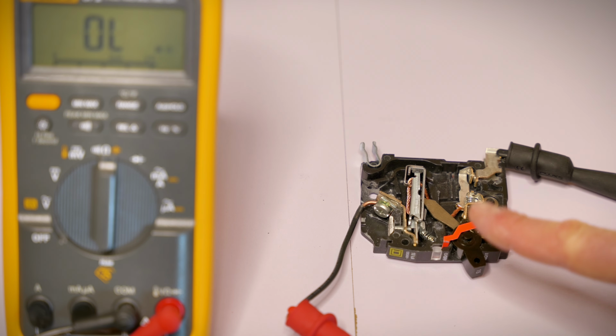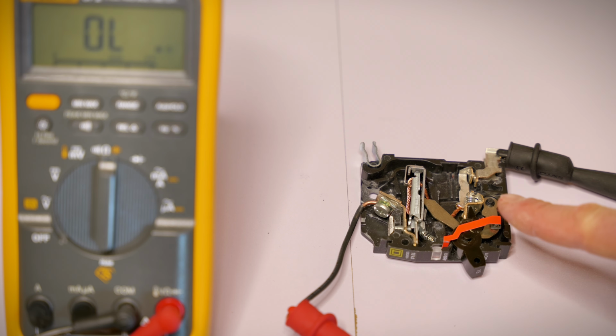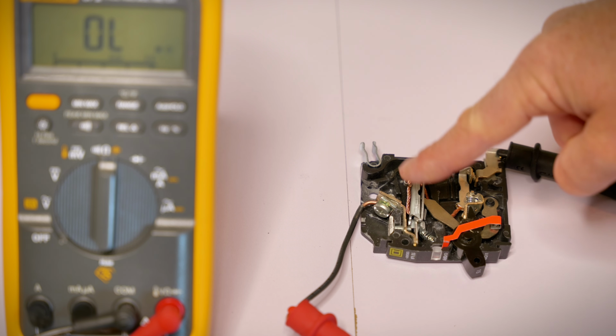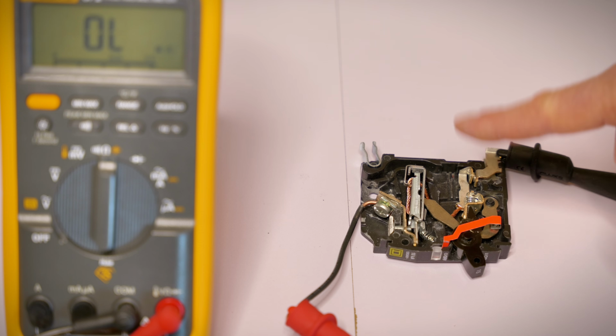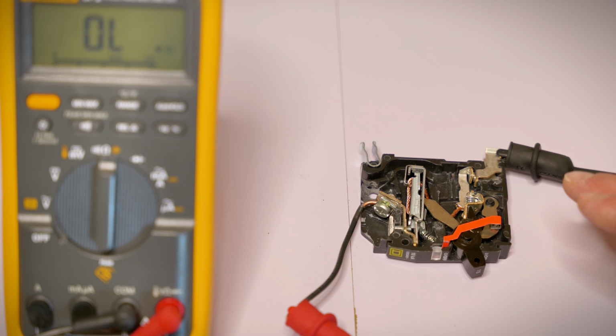As you can see, there are a lot of parts inside the moving circuit breaker, and this can cause issues when you think you have a good circuit breaker. It looks good from the outside, but you can't usually see all these internal pieces, so anything in there that breaks or is bent or is manufactured incorrectly could cause issues where you think you have a good breaker, but there's actually something defective in there.